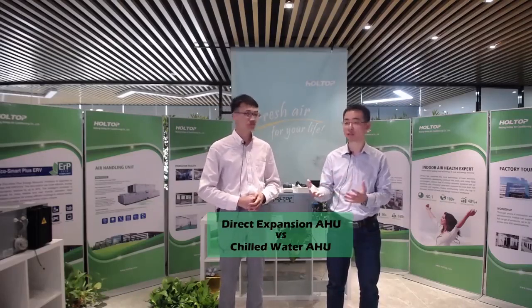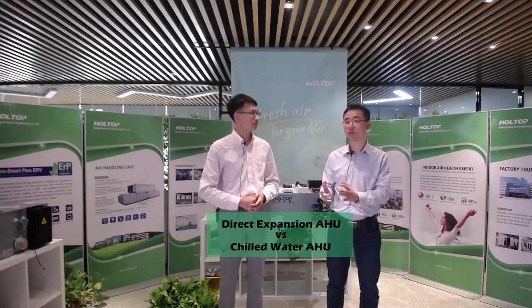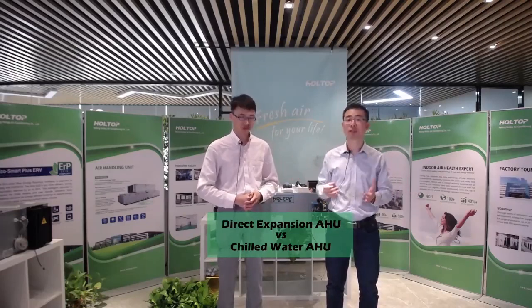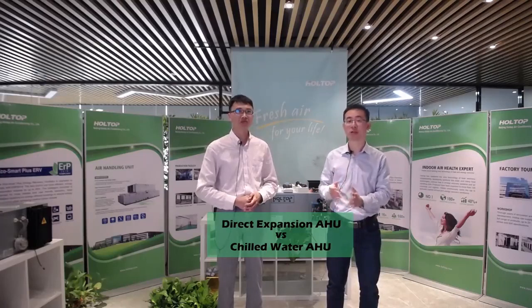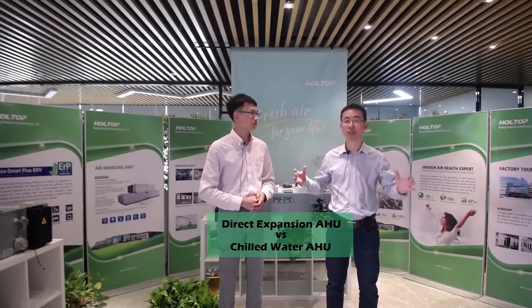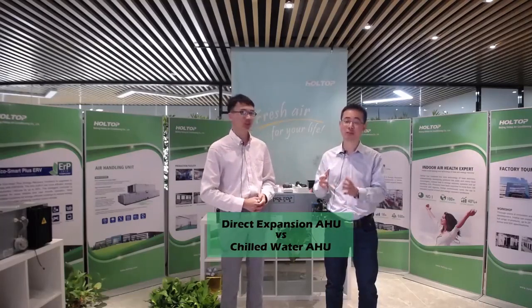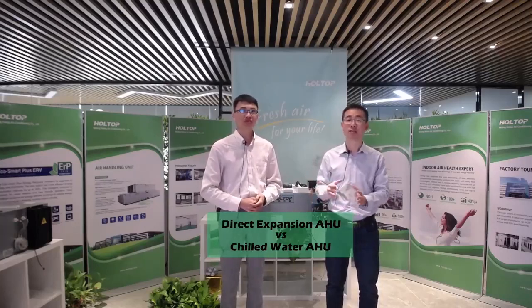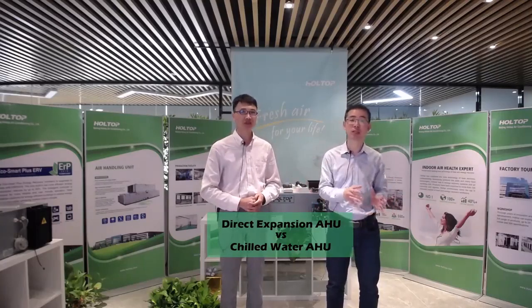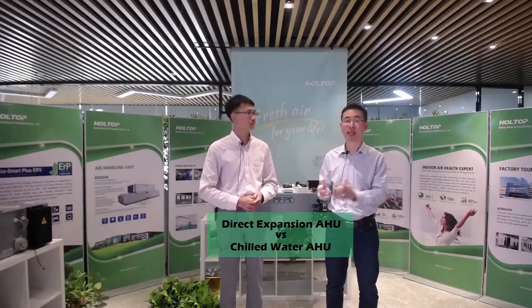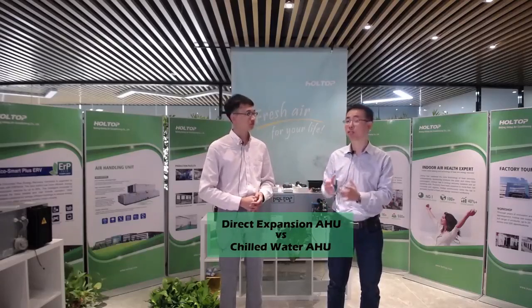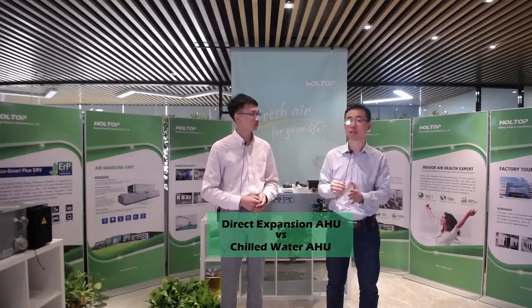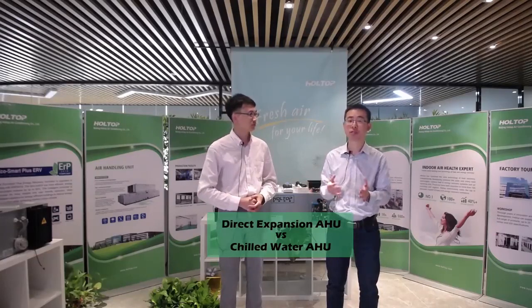Yes, because of the direct expansion versus chilled water, chilled water is actually the second heat exchange. The chilled water has to flow a long distance through the whole building. On the way, it tends to get warmer due to the friction of the flow and also because the surroundings add heat absorption. Exactly. The chilled water also has to be pumped by the water pump, which adds more heat, as the chilled water flows from the chiller to the air handling units and back again to the chiller. Apart from the heat from the air, it also absorbs a lot of additional heat, which leads to a large increase in its temperature. The chiller has to remove this additional heat from the water, which decreases efficiency, or rather additional power is required to remove this additional heat.